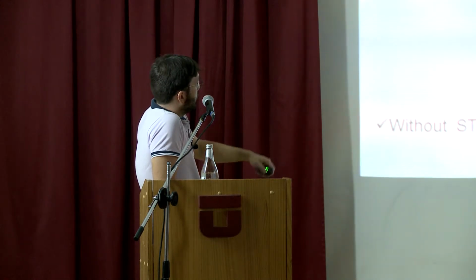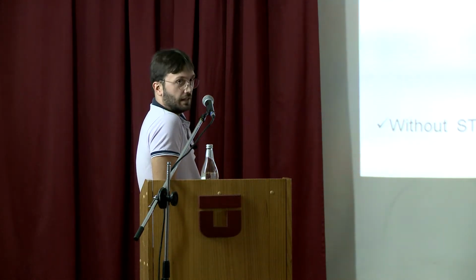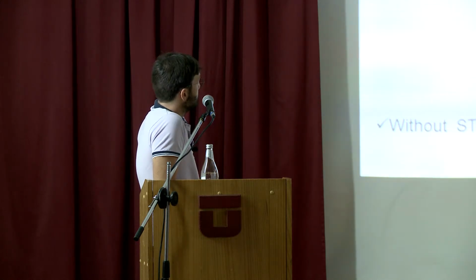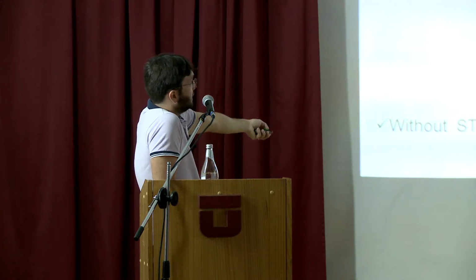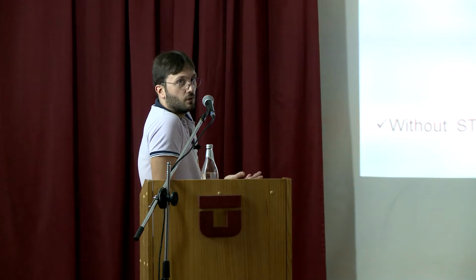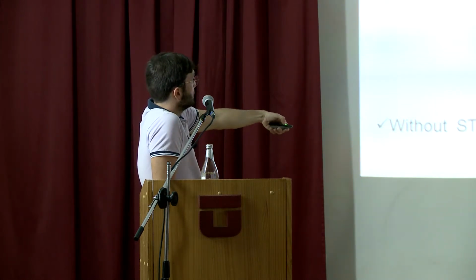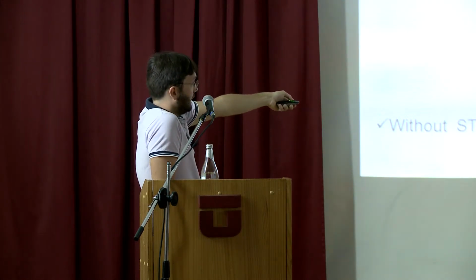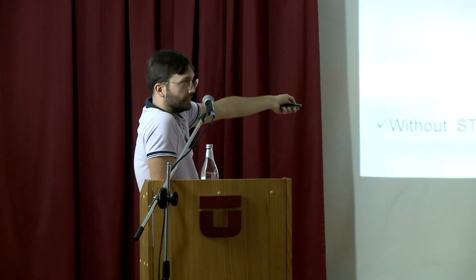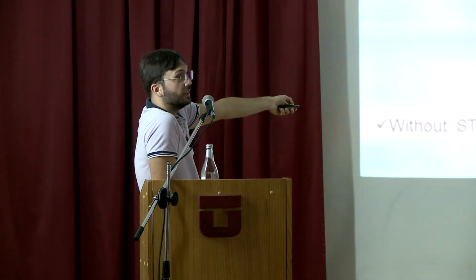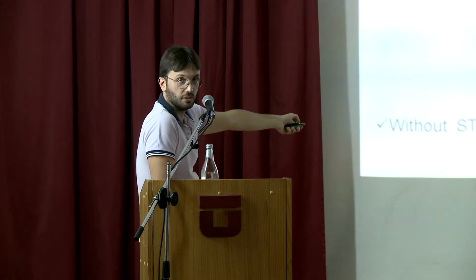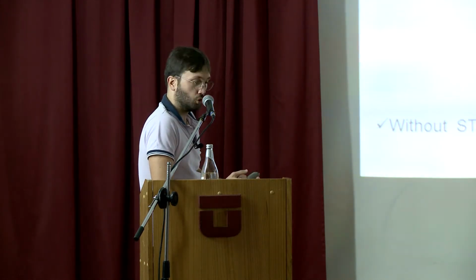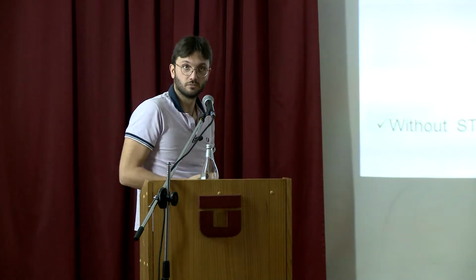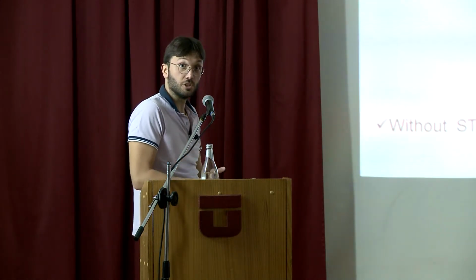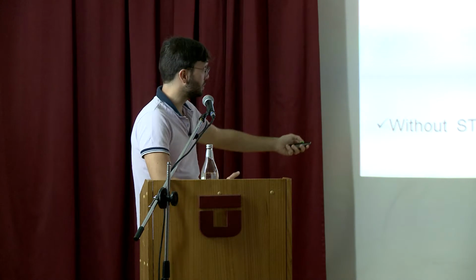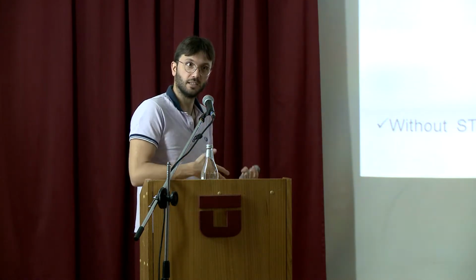So we repeat the same analysis considering the daily variation. And okay, without the ST, then we have problems. We have voltage violation. Again, voltage violation means that some of those PV or wind may disconnect. So it's not just a violation because I don't like violation. It can really be a problem because at this point, maybe something gets disconnected.